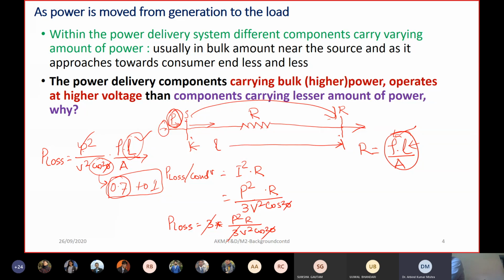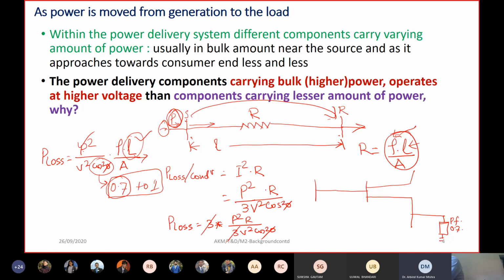Let's take an example. Suppose we have a line from here to here, and then one line goes here, another goes here, and one more goes here, and we have a demand at this point with very low reactive power. We have a load here with a low power factor of say 0.7. Now if we supply this reactive power from here itself, it's associated with some reactive power P and Q, and as you know, lower the power factor means higher the reactive power Q.